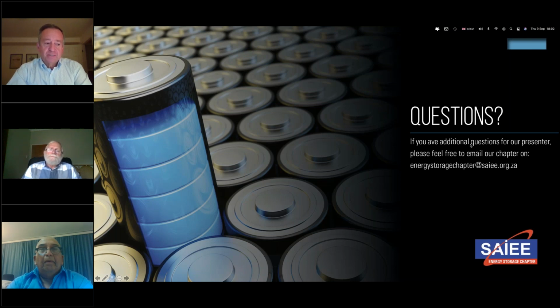Good question, I should have touched on that. Most flow batteries are not as energy efficient as lithium ion. Our round trip cycle efficiency is 70% DC-DC, including all the auxiliary loads that would be required. In the containerized solution, all auxiliary loads are inside the container, supported by the DC converters and onboard inverters. In the energy center, the building auxiliary loads are included in that 70% round trip efficiency.